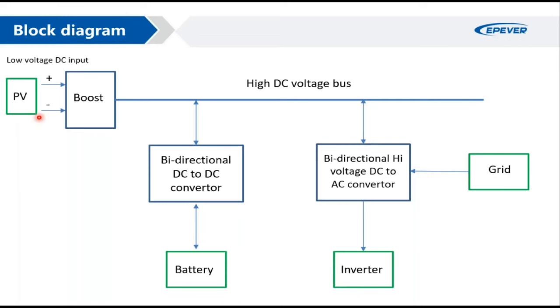A booster circuit boosts up the PV voltage to a high value, and this is distributed on a high DC voltage bus. This high voltage is used by two main components: a bidirectional DC to DC converter, and a bidirectional high voltage DC to AC converter. Since these are bidirectional, they can provide voltage to the bus or use the voltage from the bus.